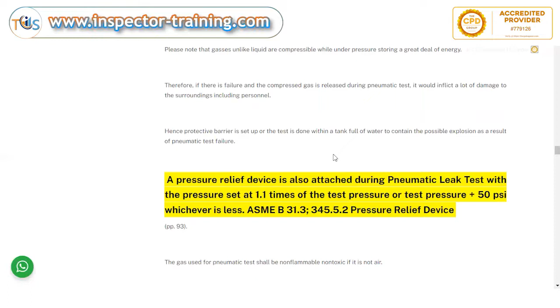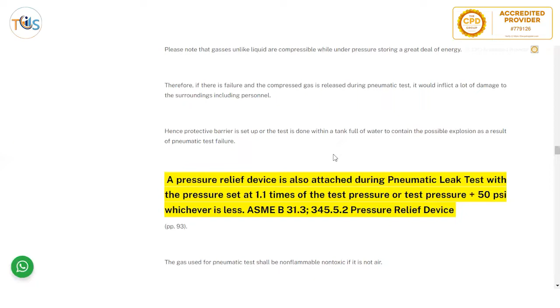So in case it goes over, the actual test pressure is 1.1 times the maximum allowable working pressure, but here you just add 50 psi to the relief valve calibration set pressure, so that if it goes beyond that 1.1 times, then it releases the pressure and there wouldn't be any danger, as a plan B. The gas used for pneumatic test shall be non-flammable and non-toxic if it is not air, and normally is nitrogen. The pneumatic test pressure shall be 1.1 times the design pressure.